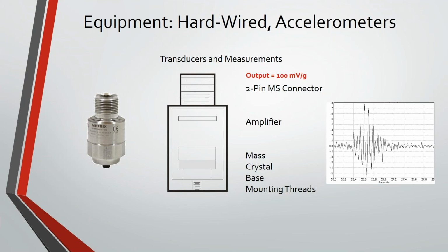A typical accelerometer is going to have a housing here. You can see in the diagram, this is what one might look like, and the housing is here. At the base of the housing, we've got the mounting threads, and then the base where we're mounting our crystal. The accelerometer is usually based on a piezoelectric crystal that generates a voltage based on the amount of force that's across it.